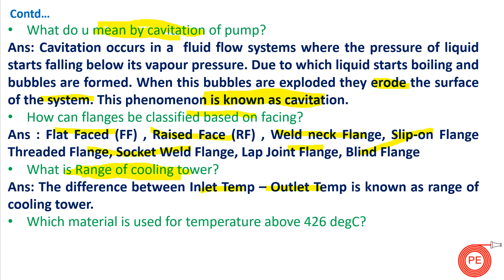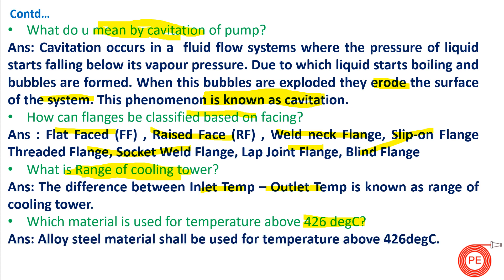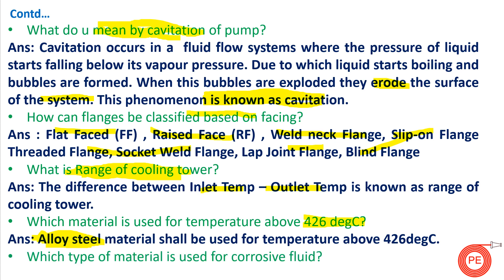Which material is used for temperatures above 426°C? For example, if you have a high pressure steam line at 426°C, which piping material do you use? We go for alloy steel material. Alloy steel should be used for such high temperature applications. Common alloy steel grades like P91 and P22 are used in steam piping, as these materials can withstand high temperature and high pressure.